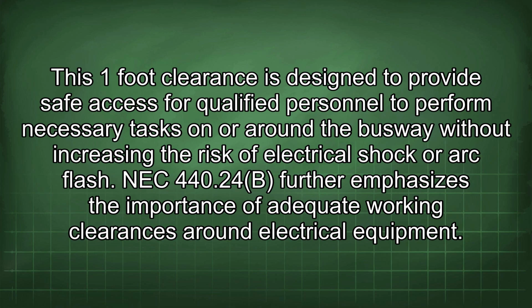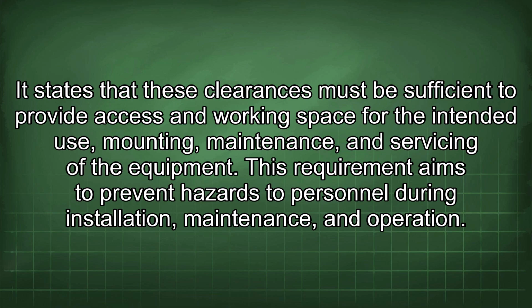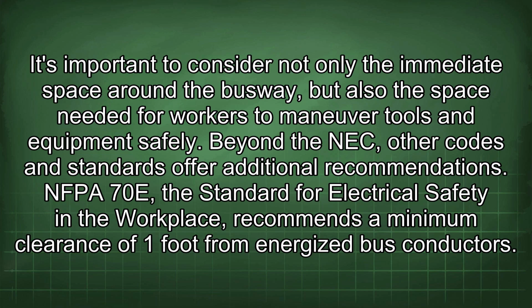NEC 440.24b further emphasizes the importance of adequate working clearances around electrical equipment. It states that these clearances must be sufficient to provide access and working space for the intended use, mounting, maintenance, and servicing of the equipment. This requirement aims to prevent hazards to personnel during installation, maintenance, and operation. It's important to consider not only the immediate space around the busway, but also the space needed for workers to maneuver tools and equipment safely.